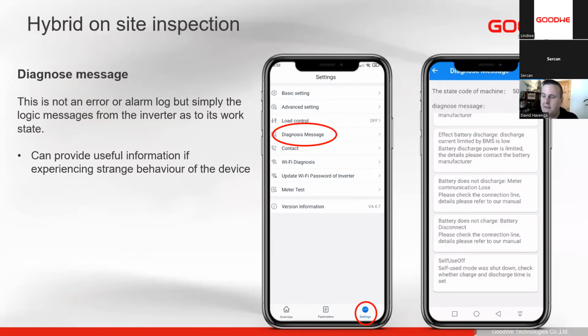Typically, you'll see it will just give messages. These messages very often do not make any sense. It might tell you SOC low when we've reached our on-grid SOC. So it's simply a setting. We've reached the set point of our battery discharge limit while on-grid, and now it says SOC low, we cannot discharge the battery further. It's basically just the logic saying, I'm not discharging the battery because the SOC is low. So all of it makes sense.